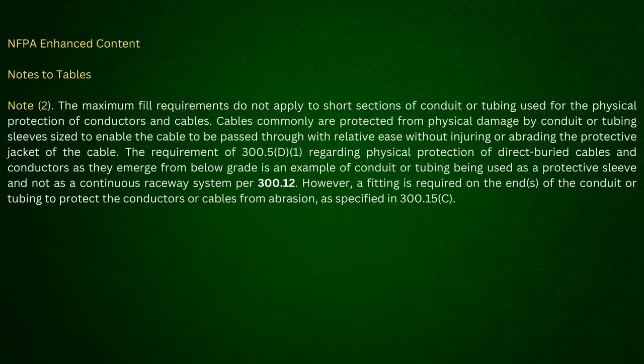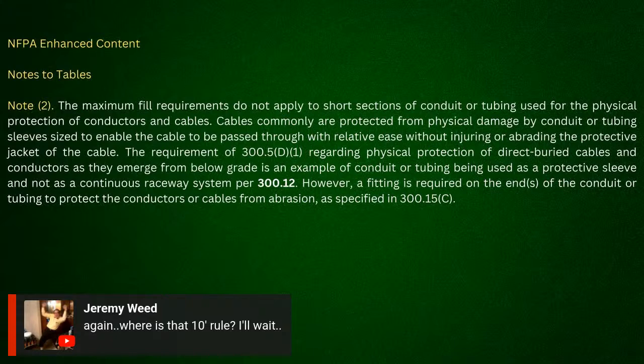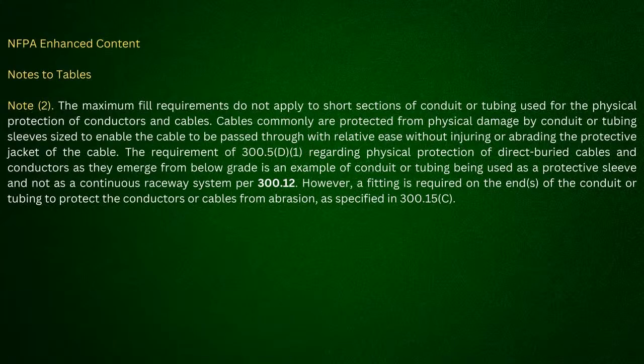The only time you're going to have that is when you're just totally packing that full with a ton of current carrying conductors. I would say, especially if you go more than 20, but I don't really see you being able to really exceed more than 20 current carrying conductors in that situation. So it's pretty interesting. I look at this from a different perspective, but when I'm looking at this, and I saw Jeremy put in here again, where's that 10-foot rule?